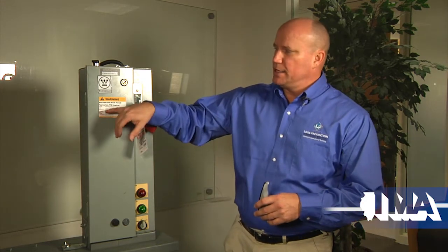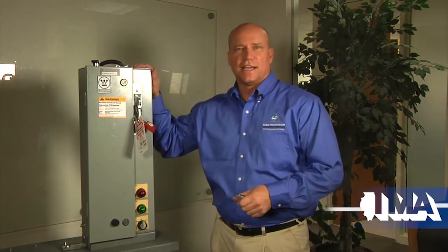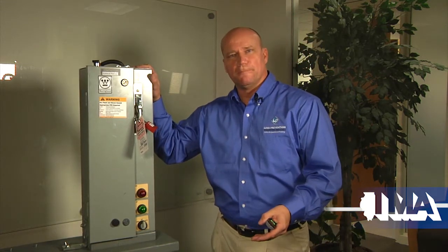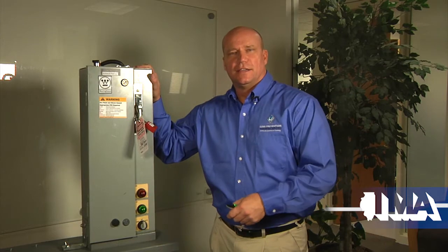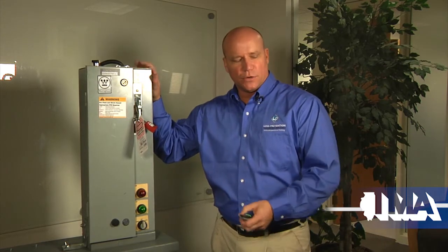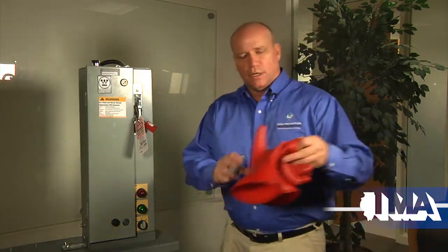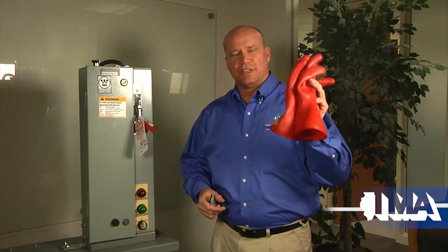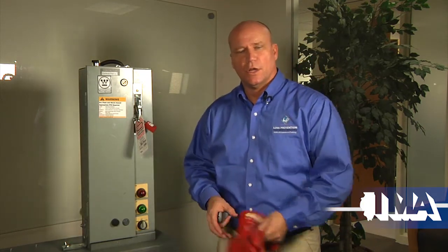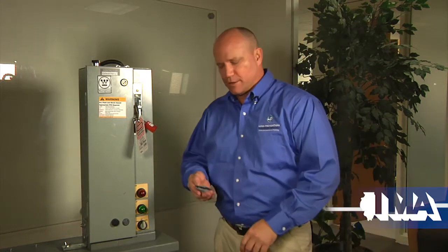The other aspect is glove selection is based on the nominal voltage value. Okay? On a label, it's going to list the highest voltage value and the type of voltage that you're going to be potentially exposed to. In this case, it's 208, and if I wore category 0 gloves, like I have right here, it would protect me from shock. Okay, so we'll walk through the actual personal protective equipment, each article of clothing or article in the ensemble that's necessary to protect you and why.